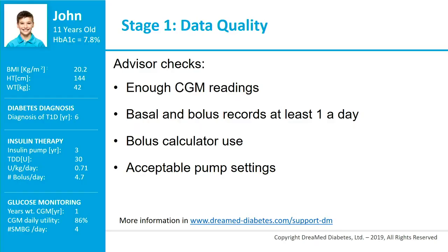And then that the pump settings already programmed into the pump are in an acceptable range. So we don't want to analyze with an algorithm, in order to be safe. We want to make sure that we are not analyzing some extreme patients, for example those that have an insulin sensitivity factor above 150 or something like that. And if you want to see more information about our safety checks, you can log into the website and see our user manual on our support page.